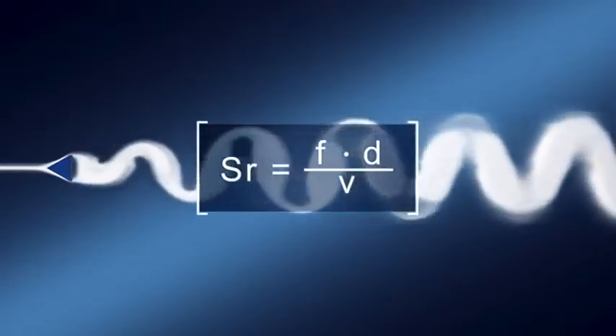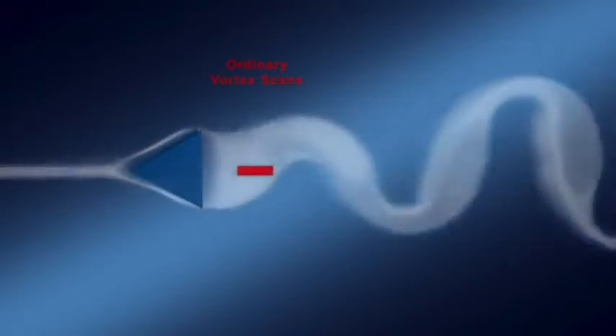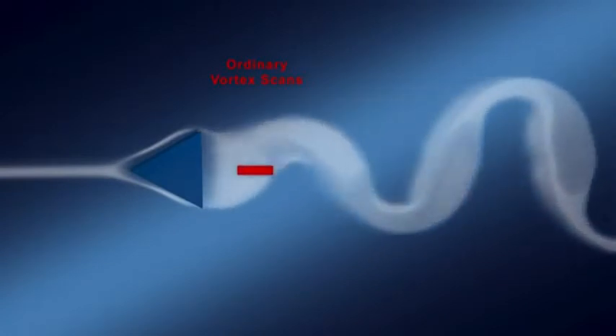The flow velocity can be calculated by determining the vortex frequency. For the measuring of gases under atmospheric conditions, ordinary vortex sensors, for example with pressure sensors, are not suitable. There is a lack of sufficient energy in the formation of the vortex street.